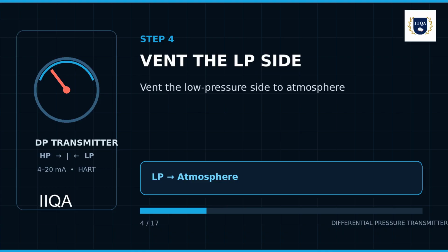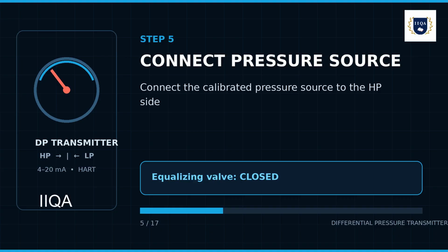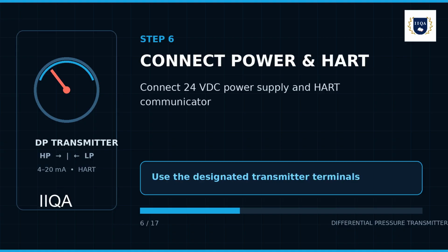valve is closed. 6. Connect a 24-volt DC power supply and a HART communicator to the designated transmitter terminals. 7. Energize the transmitter and allow sufficient warm-up time for stabilization. 8. Verify the calibrated range, LRV, URV, from the instrument data sheet and transmitter configuration.